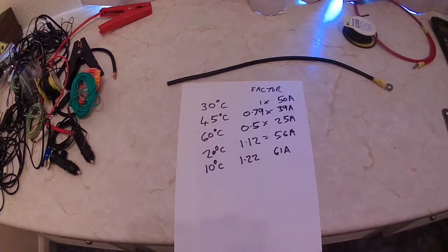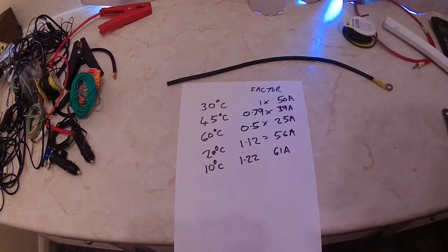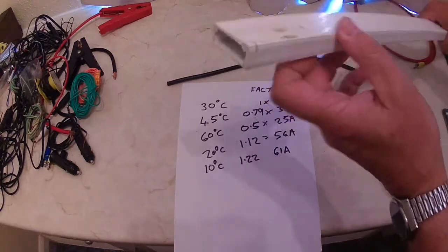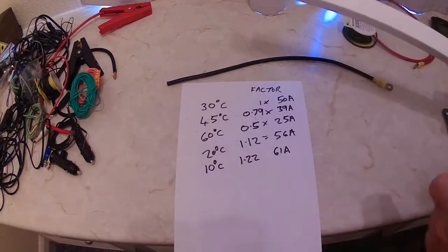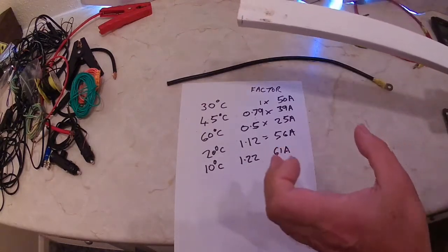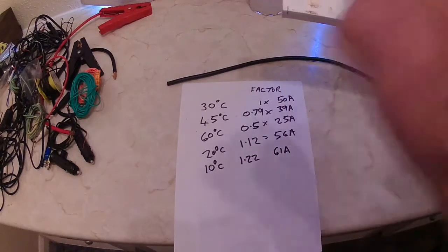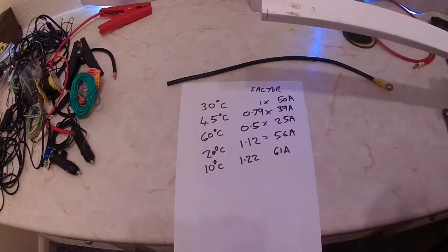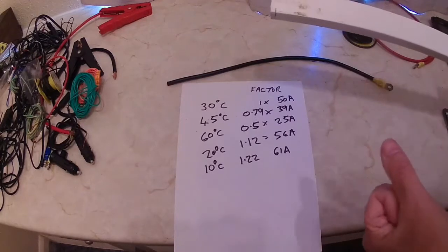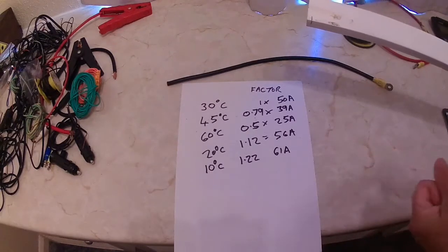When you start putting your cables behind the insulation of your van, or behind panelling, or you run it in ducting, whether the ducting is plastic or metal conduit or metal trunking, and also if cables are bunched together, tied together with tie wraps or wrapped up with insulation tape or whatever, then they're not in ambient temperature anymore. They're not in free air.